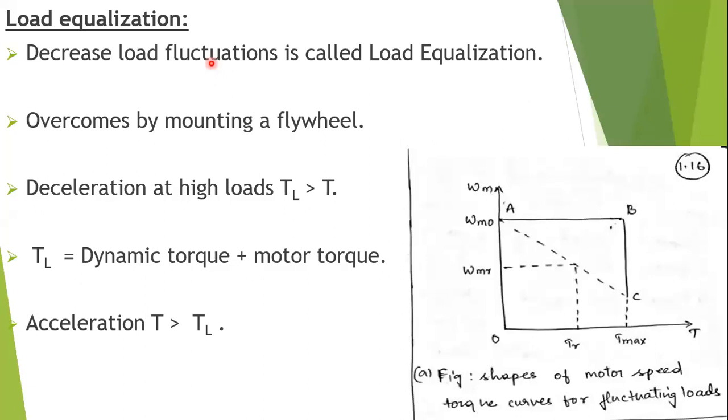In order to overcome these load fluctuations, we have to mount a flywheel. A flywheel should be mounted on the motor shaft in non-reversible drives only. There are reversible drives and non-reversible drives. In non-reversible drives, we take a flywheel and mount it onto the shaft of the motor.